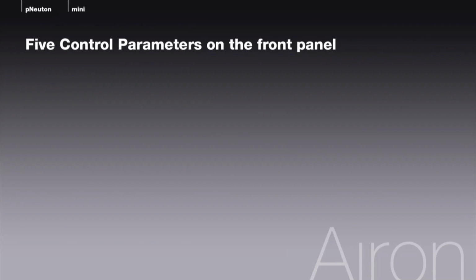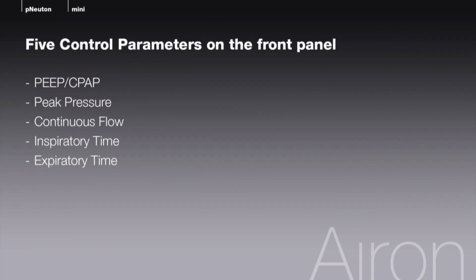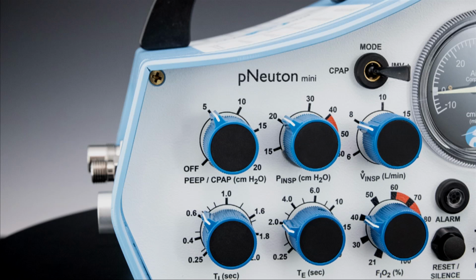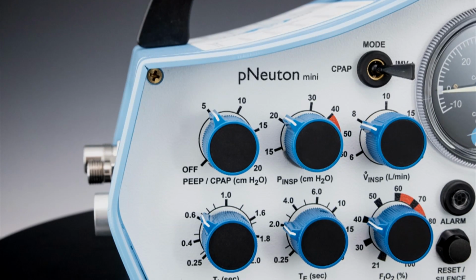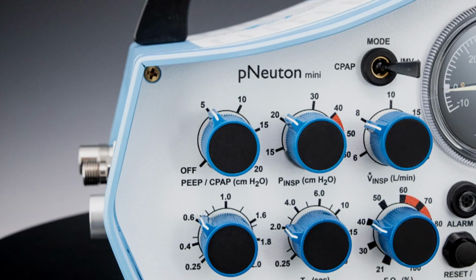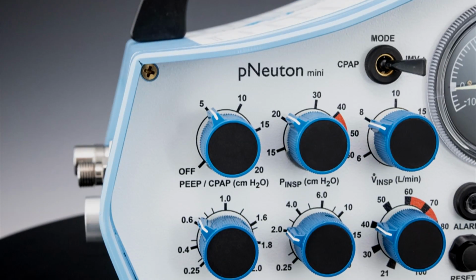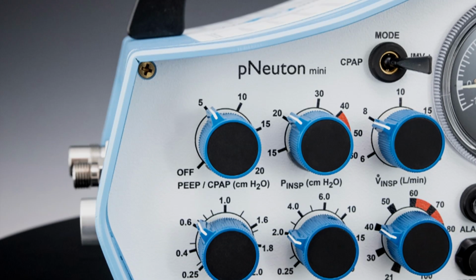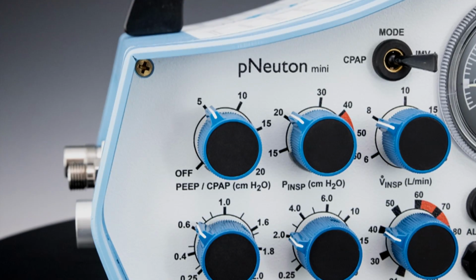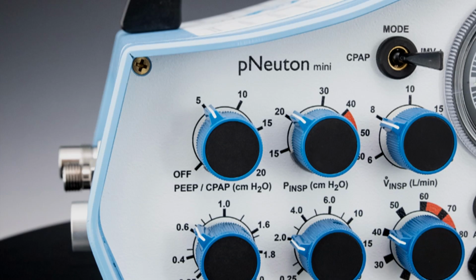First, let's review the 5 control parameters related to patient respiratory support: PEEP CPAP, peak pressure, continuous flow, inspiratory time, and expiratory time. PEEP CPAP control. Let's start at the upper left side with the control that provides both PEEP and CPAP. When the device is set for ventilation mode, PEEP will provide the baseline pressure. When not in ventilation mode, it supports CPAP for spontaneous breathing.